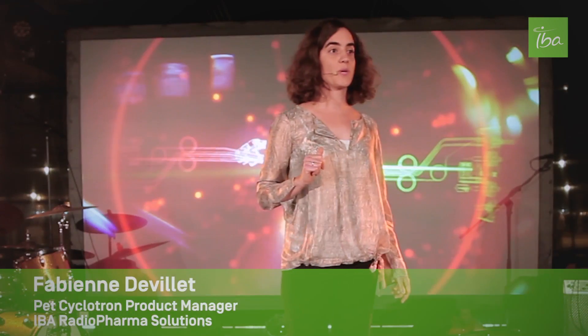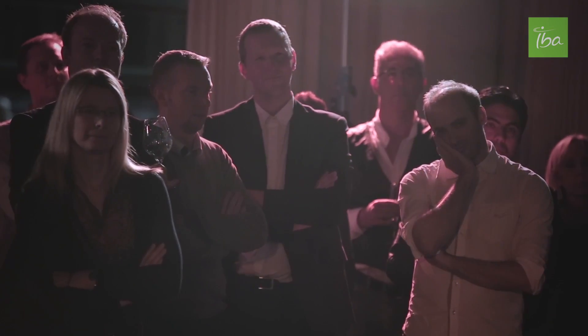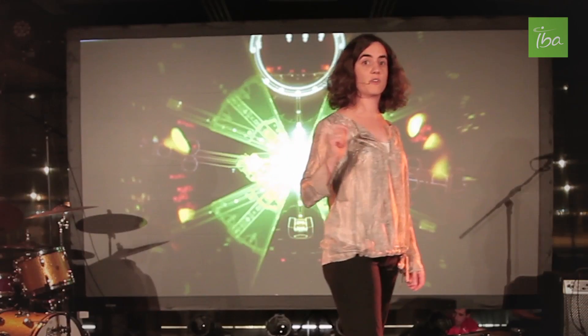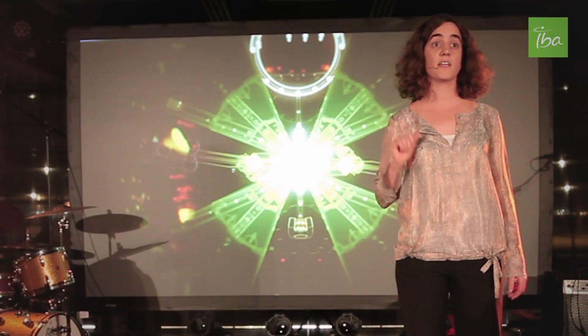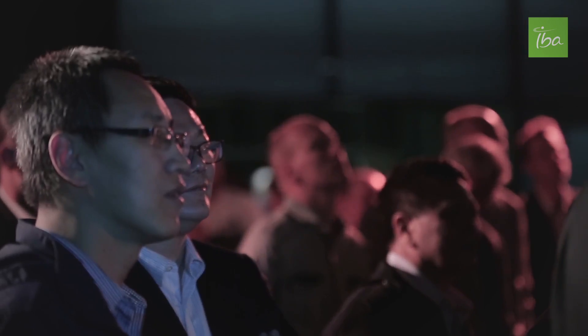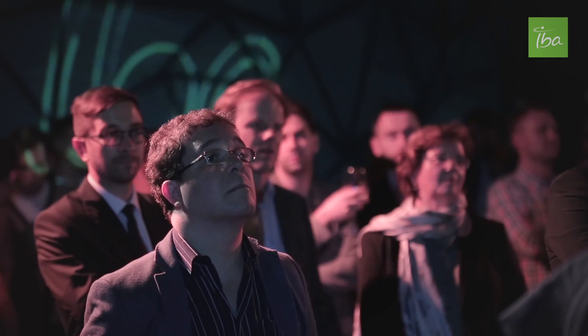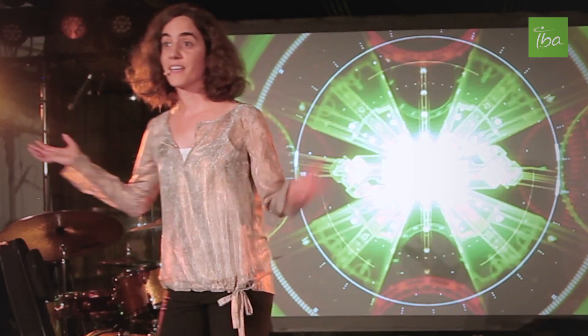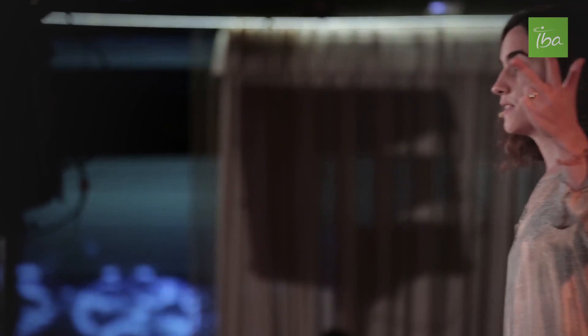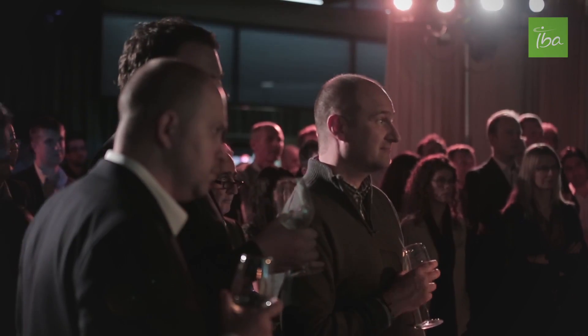We wanted to create the most powerful mid-energy cyclotron on the market. Today, we are very proud to announce a performance never achieved on an internal source cyclotron. It's not 200 microamps, not 220, not 250 — but the Cyclone Cube will be able to deliver up to 300 microamps. Can you imagine 300 microamps? Enough activity for up to 300 FDG doses.